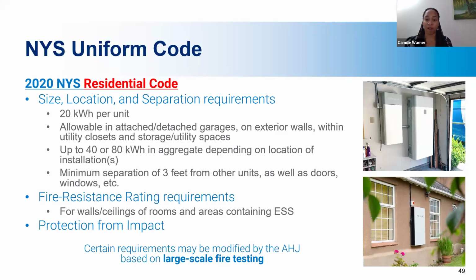The code also talks about fire resistance ratings that are required for the walls and ceilings for any room or area that contains these systems. And as I mentioned before, if a residential system opts to take the 9540A destructive test method, and that test says, for instance, that this energy storage system doesn't need to be kept 3 feet away, it can be kept 2 feet away, that can be waived based on the results of large-scale fire testing.